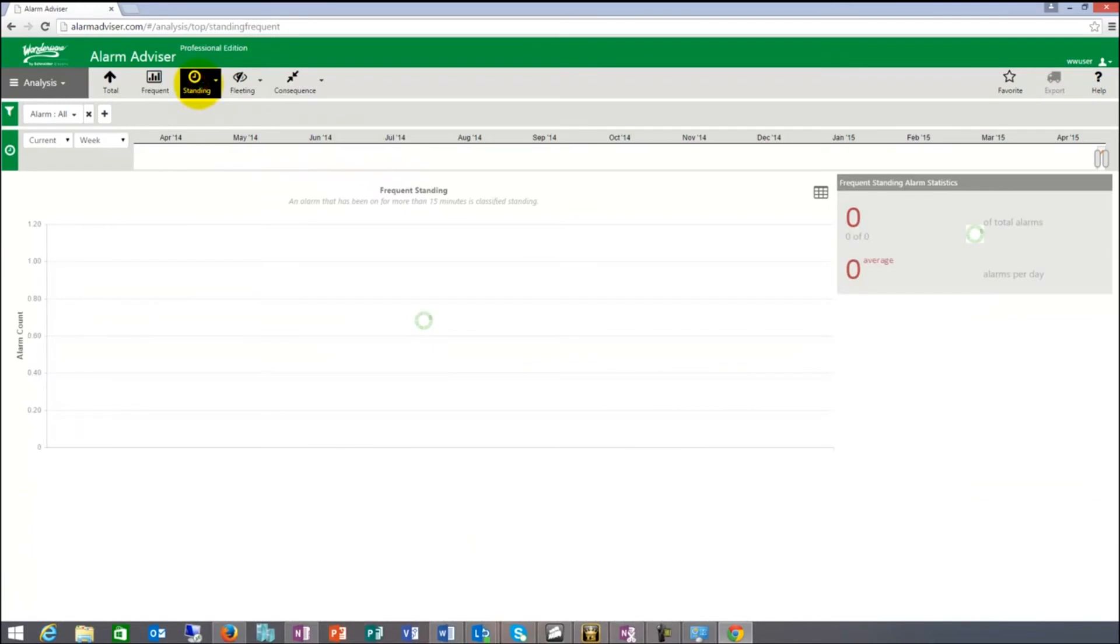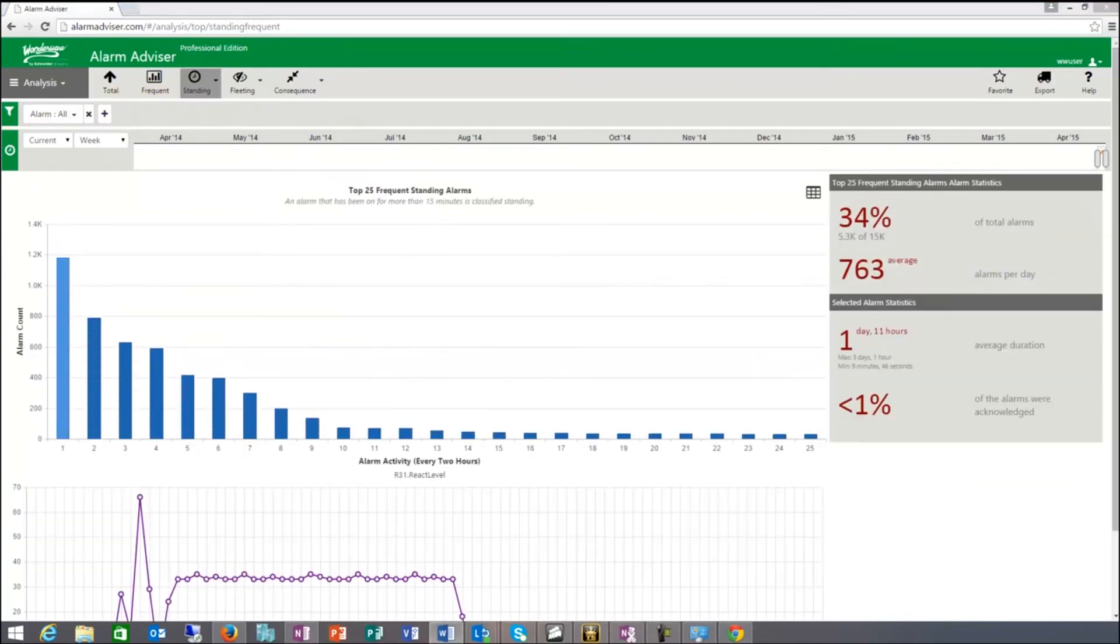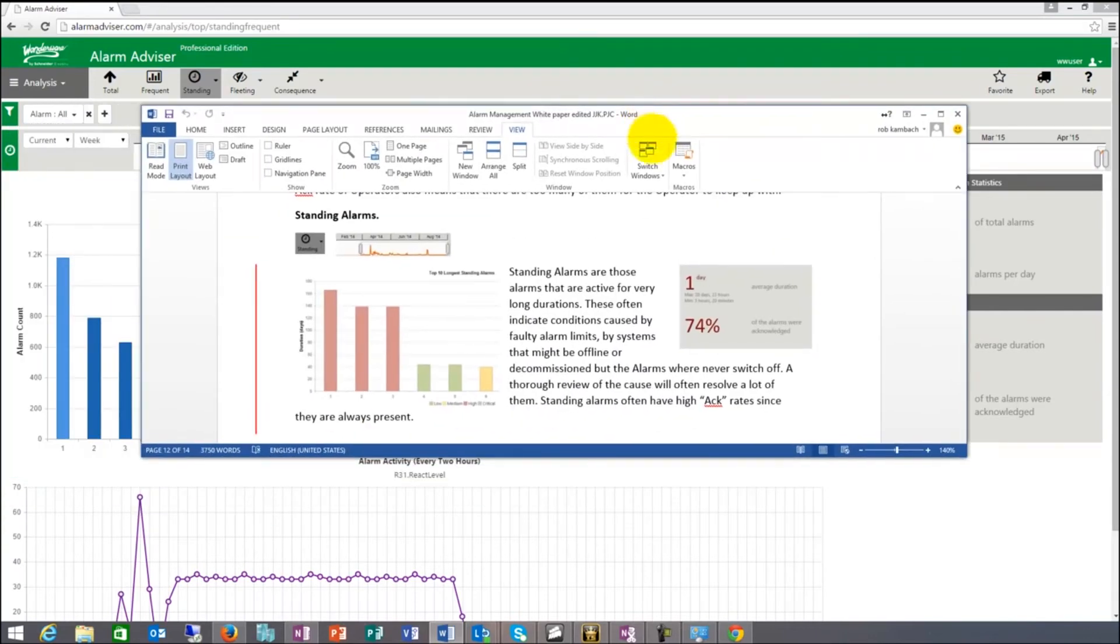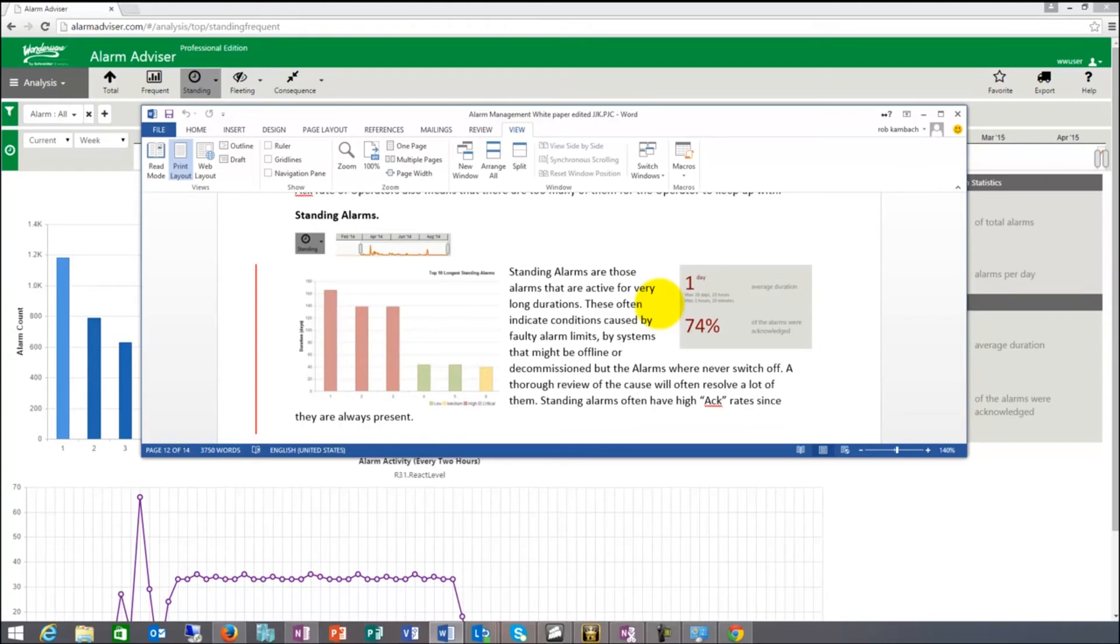Standing alarms are different. If we take a look at standing, standing alarms are those alarms that are active for very long durations. These often indicate conditions caused by faulty alarm limits, by systems that might be offline. Things that you could use here are plant state suppression, you could use shelving, you could use tools to tell the system that these systems are offline so they don't have all these standing alarms all the time. It might be also decommissioned, but the alarms were never switched off. A thorough review of these will often resolve a lot of them.